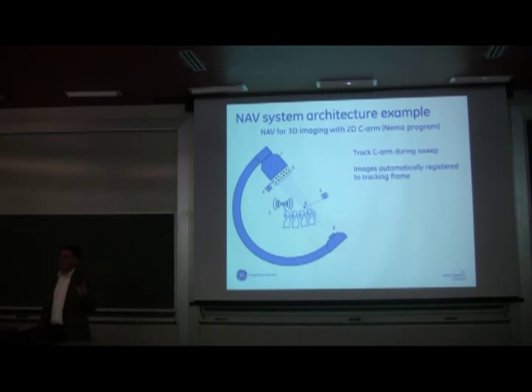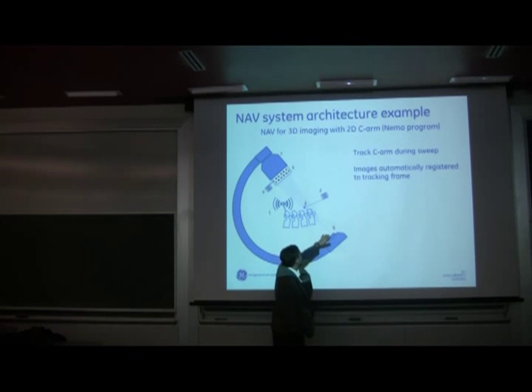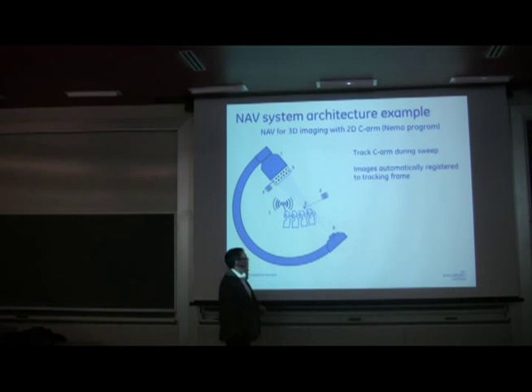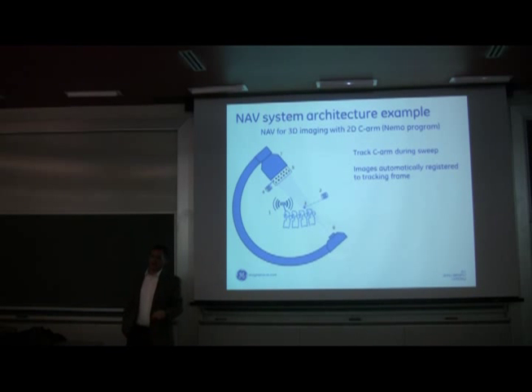There are a couple of things that you need to do with an X-ray machine to make the X-rays usable. The first is you need to understand the conic projection. You can imagine that this triangle, or this cone, the projection, depends on any mechanical deflection of the C, any kind of translation of the source relative to the detector. And this all has to be calibrated and well known for the system to operate in its augmented reality fashion.